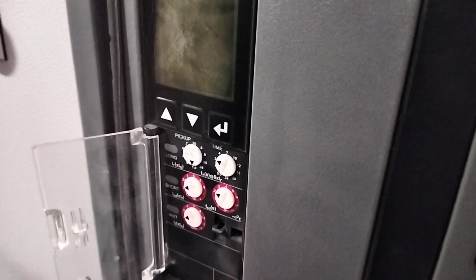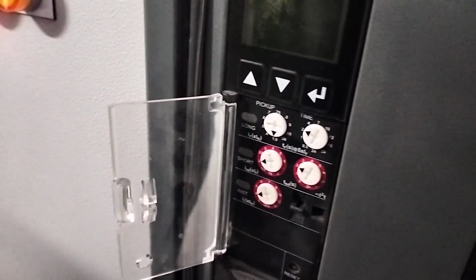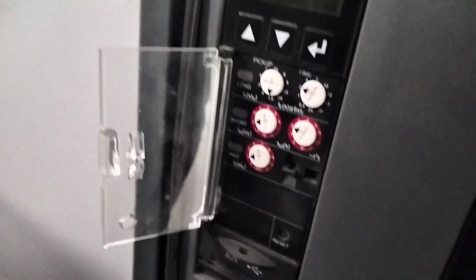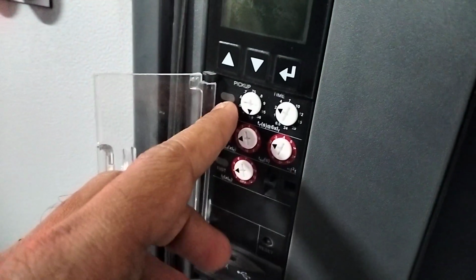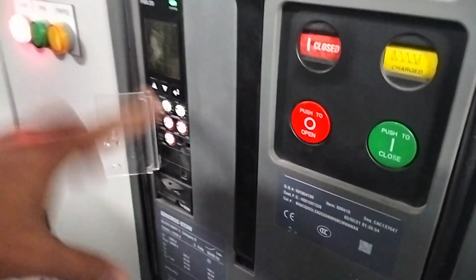No, 0.4 means around how much? Of 2500, 0.4 is how much? 1000 ampere. 1000 ampere will come. So you can set 0.4, 0.5, 0.6, 0.7, 0.75. You can adjust your settings. Now it is kept at full.